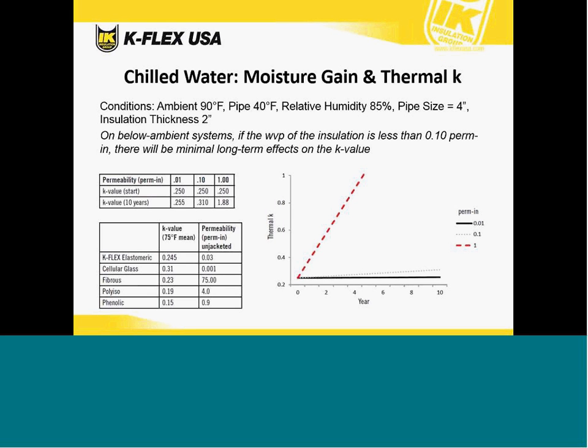So, important. This shows the effect of thermal K on an insulation system over time. In this scenario, the conditions include an ambient temperature of 90 degrees Fahrenheit, a process temperature of 40 degrees Fahrenheit, and a relative humidity of 85%. So this would be an outdoor application. Pipe size of about 4 inches, and insulation thickness of 2 inches. And what we show here is that over time, the system with a higher water vapor permeability will eventually get a higher thermal K due to moisture intrusion in that system.